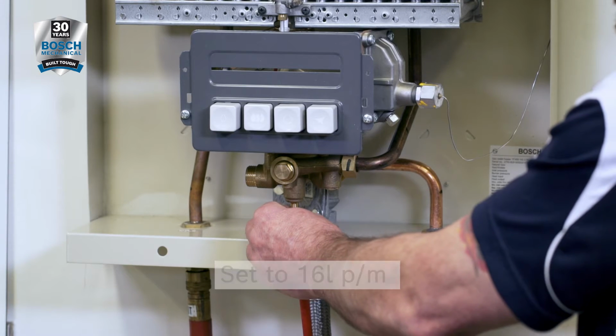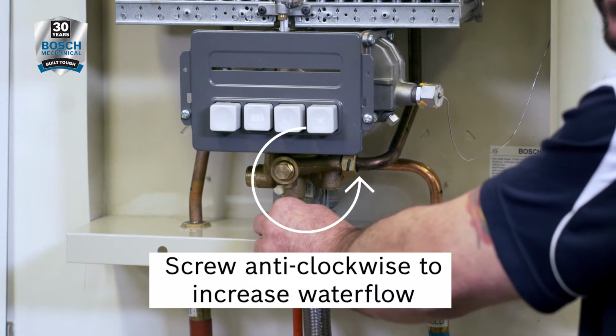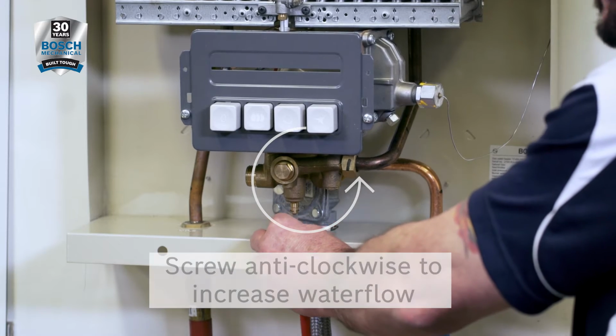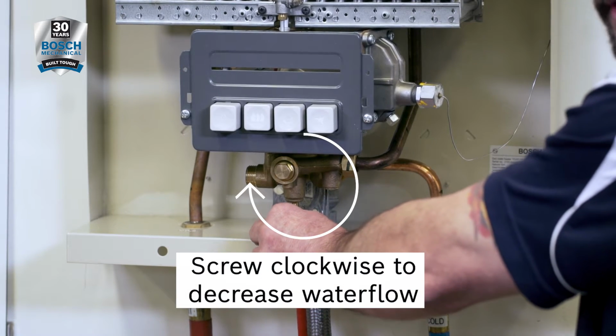By adjusting the screw anti-clockwise away from the water valve, that'll increase your water flow. Winding it clockwise into the water valve will decrease your water flow.